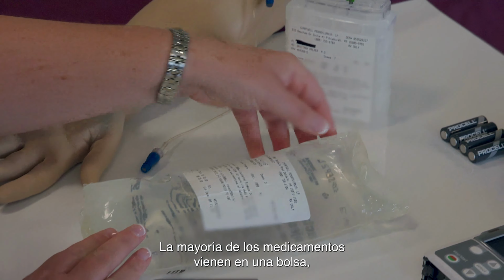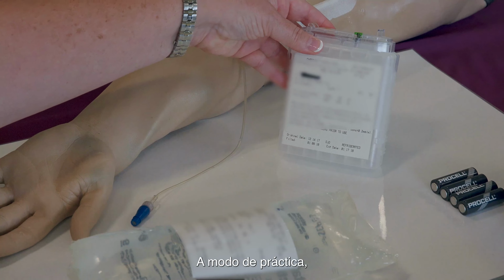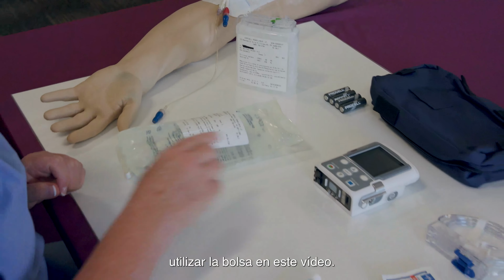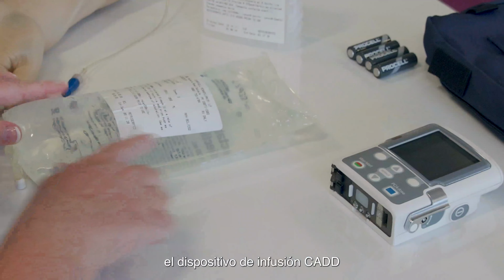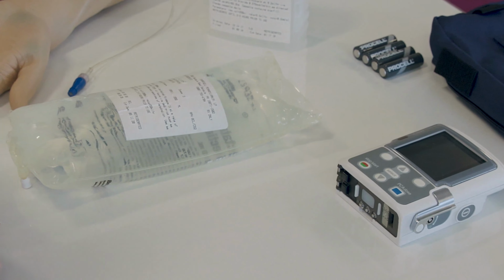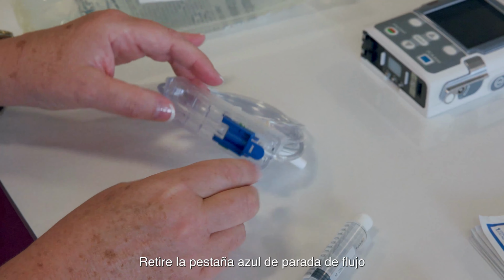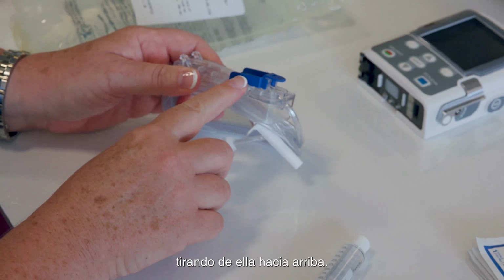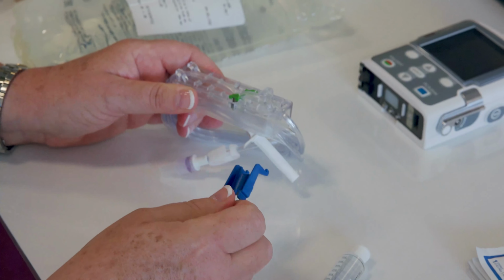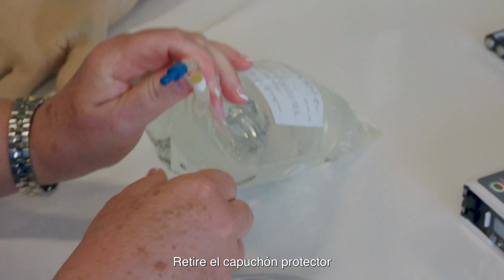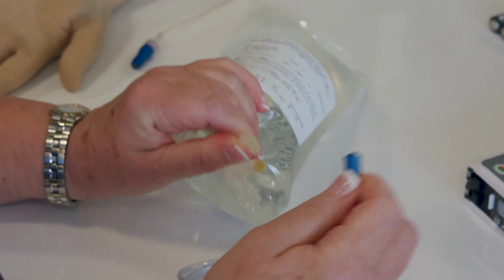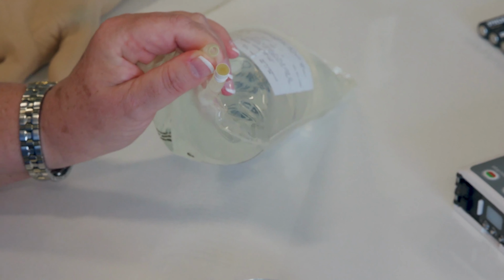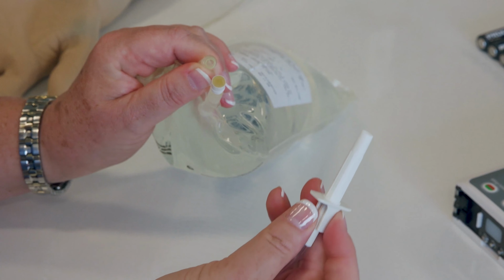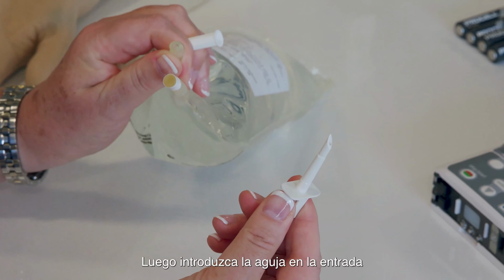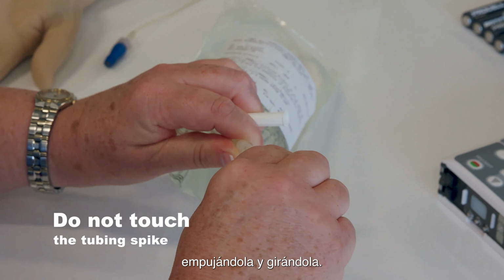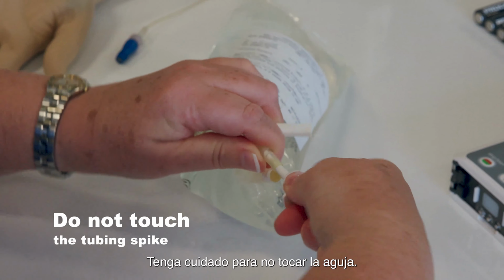Most medications will come in a bag, but some may come in a cassette. For training purposes, we will demonstrate using a bag in this video. You will be required to connect the CADD tubing to your medication bag. Remove the blue flow stop device from the tubing cassette by pulling it upward. Remove protective tab from entry port of medication bag. Remove cover from the tubing spike, then insert the spike into the entry port using a pushing, twisting motion. Be careful to not touch the spike.